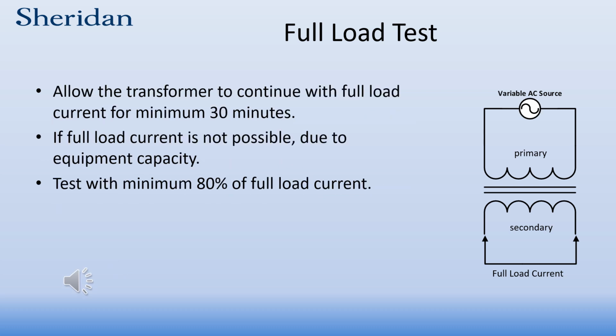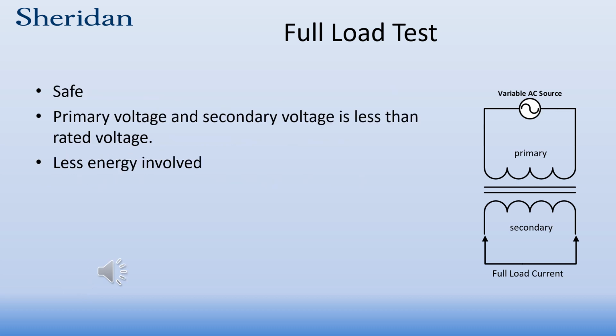Once you have the conditions set, allow the transformer to continue with full load current for a minimum of 30 minutes. Now, a good hour is actually recommended, but with 30 minutes, you'll be passing full load current. The transformer's under maximum stress. If the full load current is not possible because you have limitations of your variable voltage power supply, you must at least test it with a minimum of 80% of full load current in order for this test to do any good. The transformer should get warm under this type of load, if not hot.